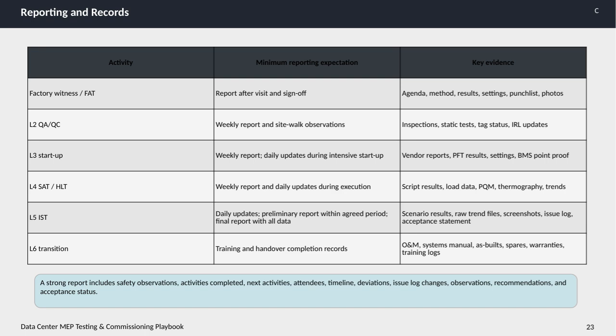The supporting evidence documented includes script results, load data, power quality monitoring, thermography, and trend analysis to thoroughly assess system performance under stress conditions. Level 5 integrated systems testing requires even more frequent updates with daily reports and both preliminary and final comprehensive reports.